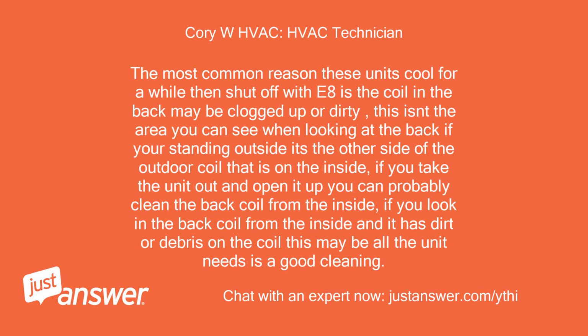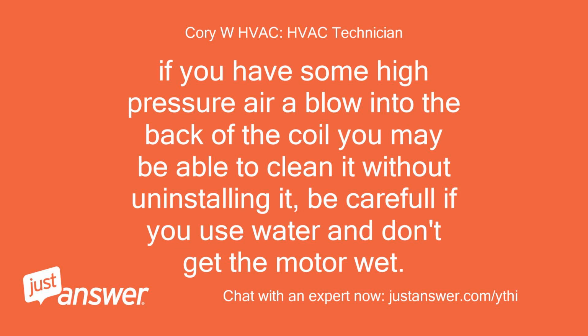The most common reason these units cool for a while then shut off with E8 is the coil in the back may be clogged up or dirty. This isn't the area you can see when looking at the back if you're standing outside, it's the other side of the outdoor coil that is on the inside. If you take the unit out and open it up, you can probably clean the back coil from the inside. If you look in the back coil from the inside and it has dirt or debris on the coil, this may be all the unit needs is a good cleaning. If you have some high pressure air, blow into the back of the coil, and you may be able to clean it without uninstalling it. Be careful if you use water and don't get the motor wet.